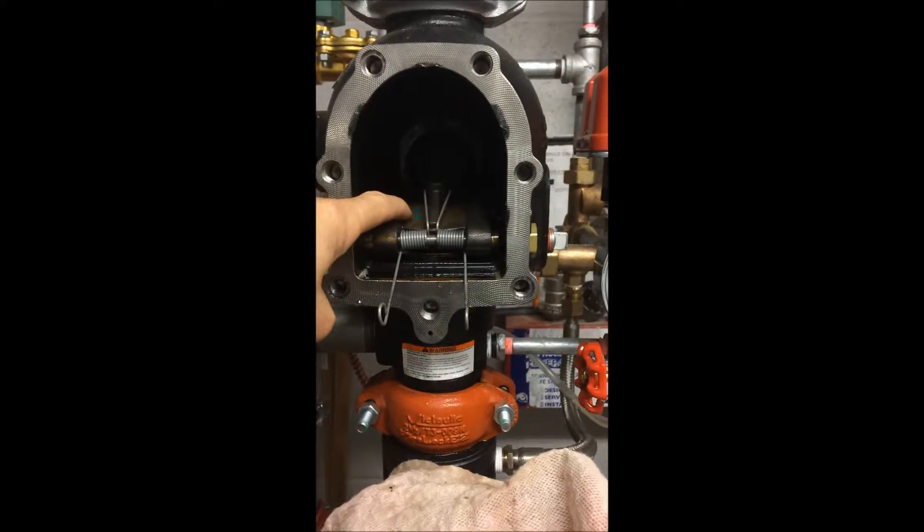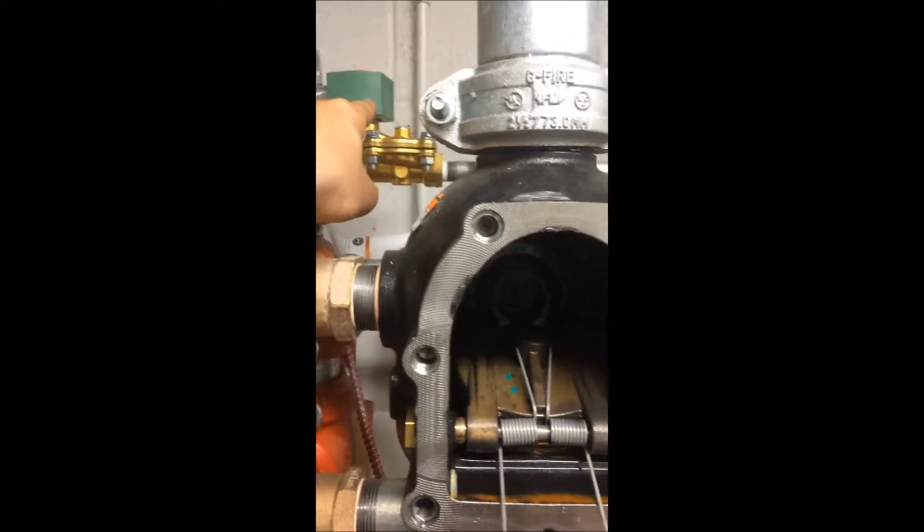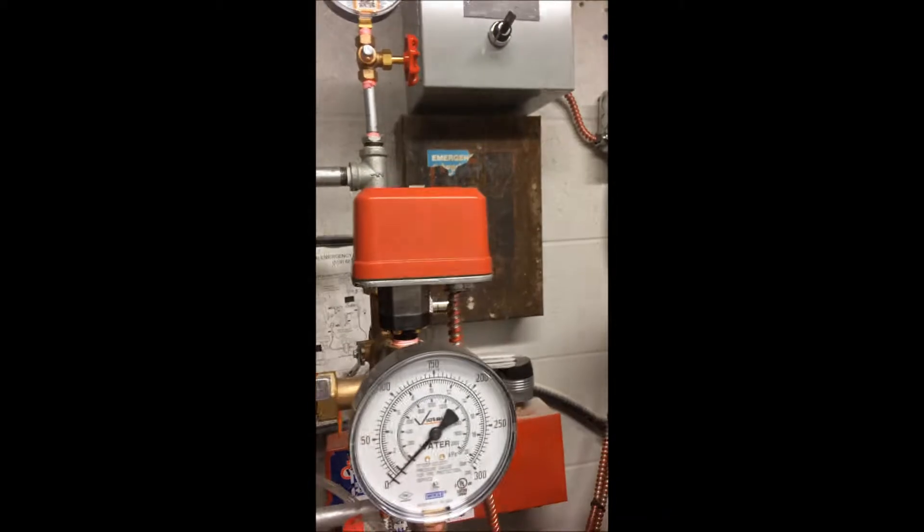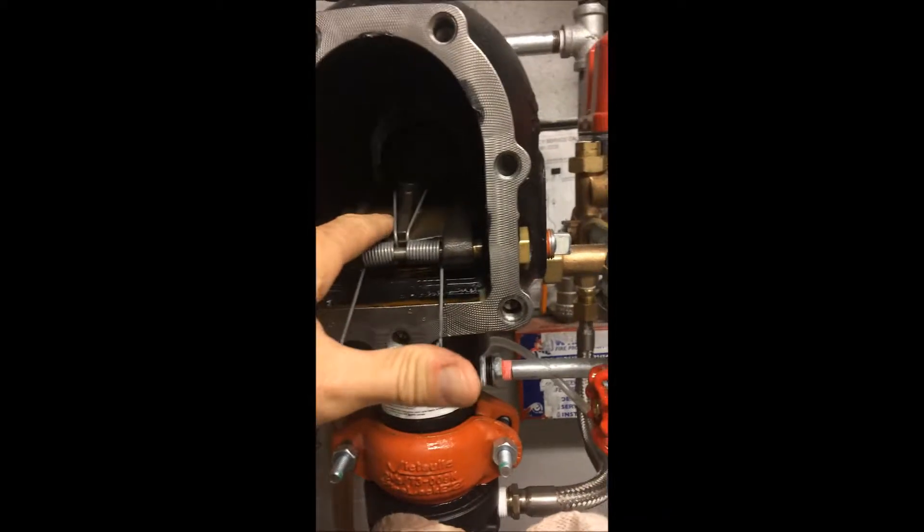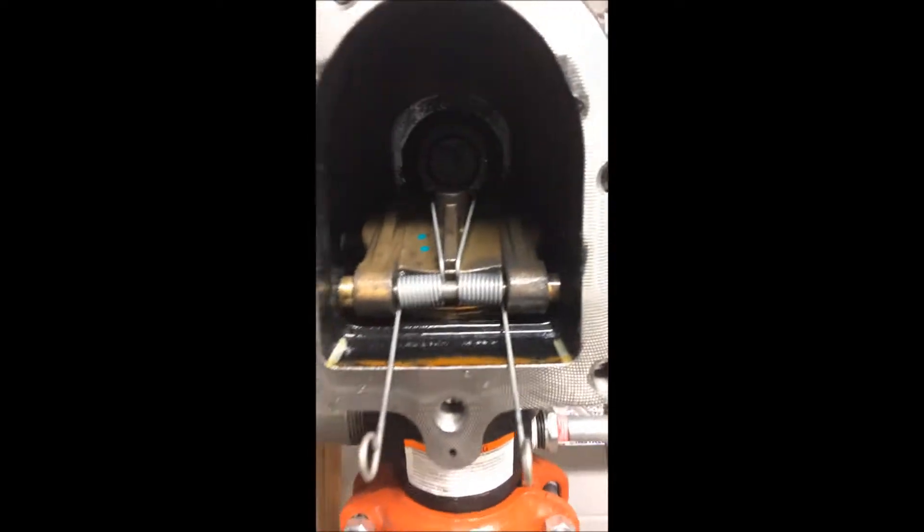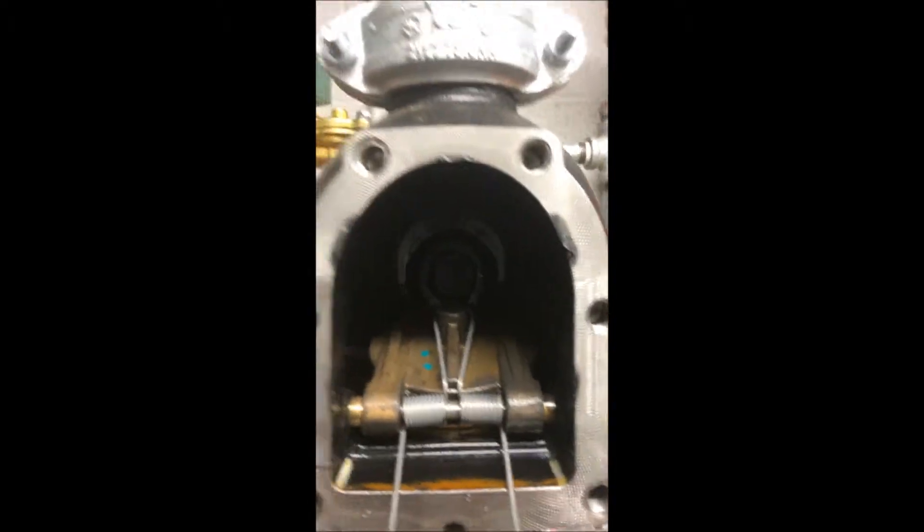Well, the problem is the solenoid is working here. It's fine. I have the pressure operating now because I have the valve open. But what's happened is sometimes the clapper gets caught up on the actual latch. And it won't reset.